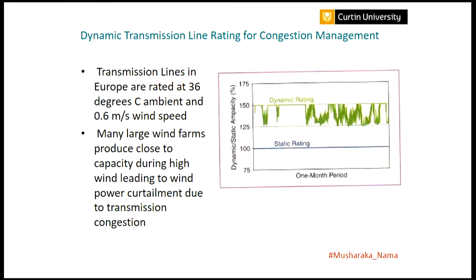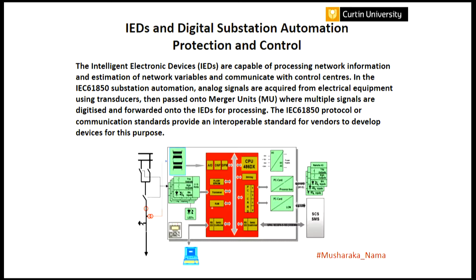Substations are changing, becoming digital, and relying on the IEC 61850 protocol. Now substations are monitored and interacted with digitally, saving space. Many of the small wires connecting relays and units together can now be handled by a single pair of fiber optics, eliminating that maze of wiring. This makes for a smaller substation footprint and much easier maintenance, as anyone who's worked in a substation with all those cables knows.